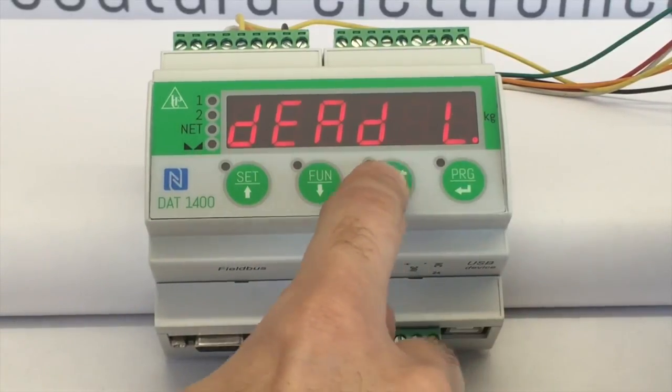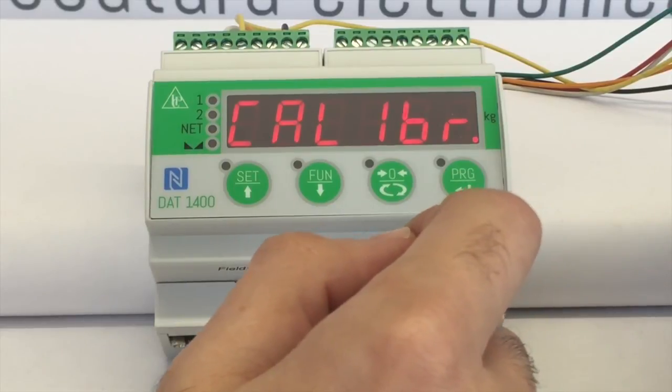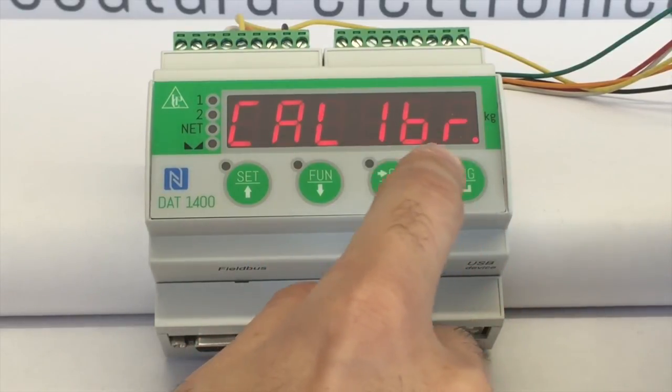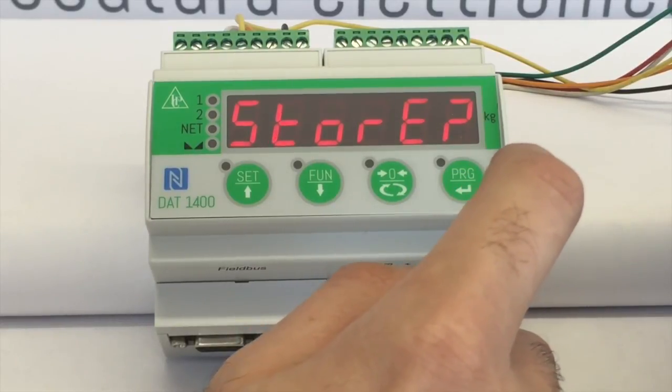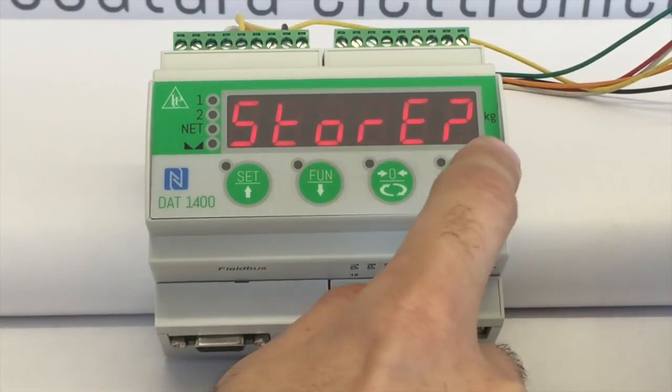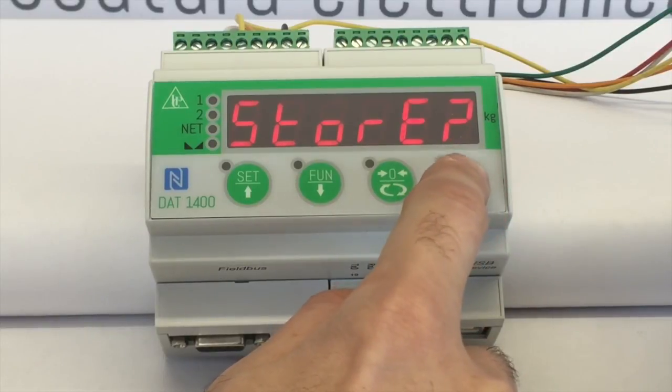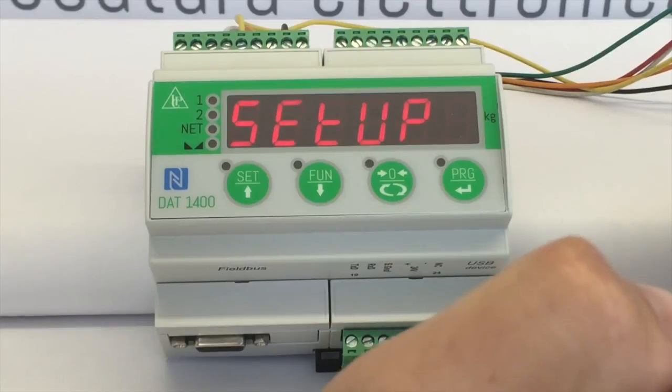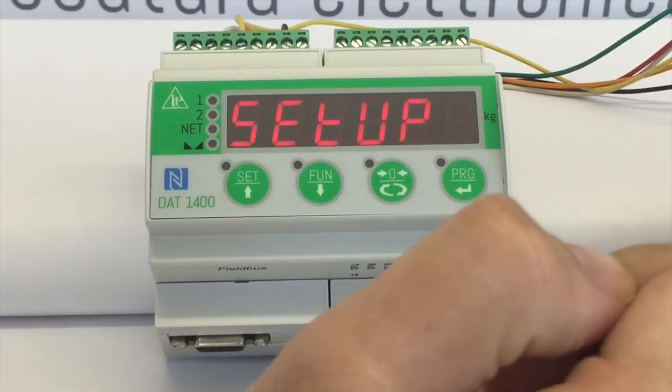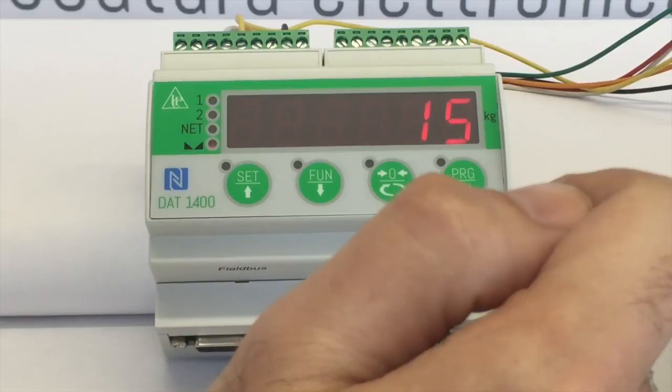Now you can exit the menu by pressing in sequence, 0 and calibre will appear on the display. Press 0 again to show STORE with a question mark. To apply changes, press PRG for 2 seconds. The display will show SETUP. Press once the 0 button to exit the menu and return to weighing.